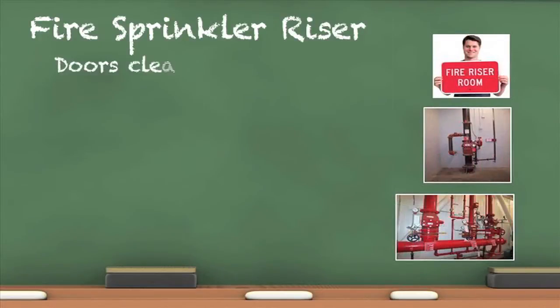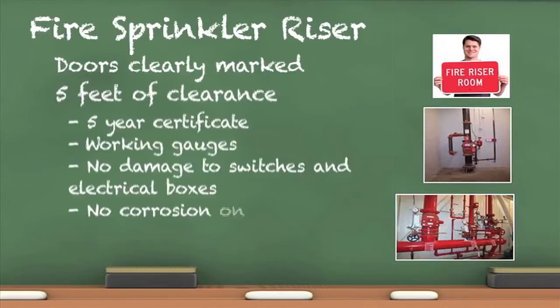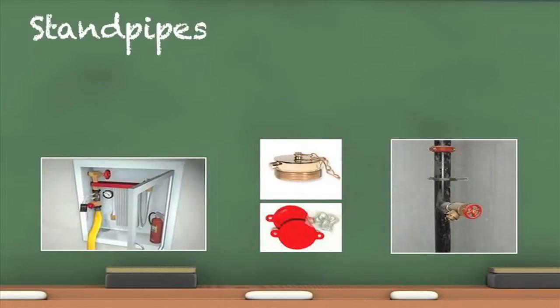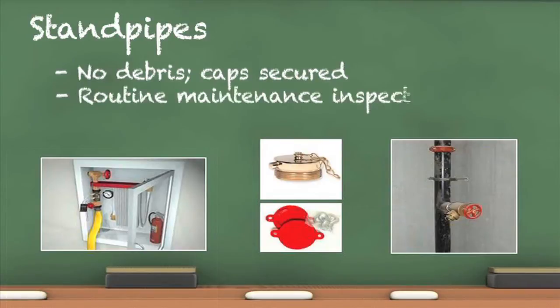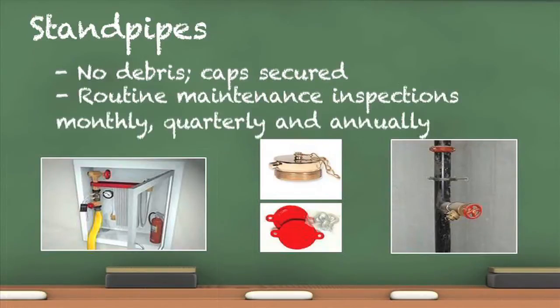Doors to riser rooms should be clearly marked and the rooms themselves free of storage. The equipment is required to have at least 5 feet of clearance in all directions. The 5-year certification sticker is required to be affixed to the riser. Nothing can be attached to any portion of this system at any time. Interior standpipes have the same requirements as exterior standpipes — there should be no debris inside the inlet and caps must be securely affixed. Nothing can be attached to any component of this system.